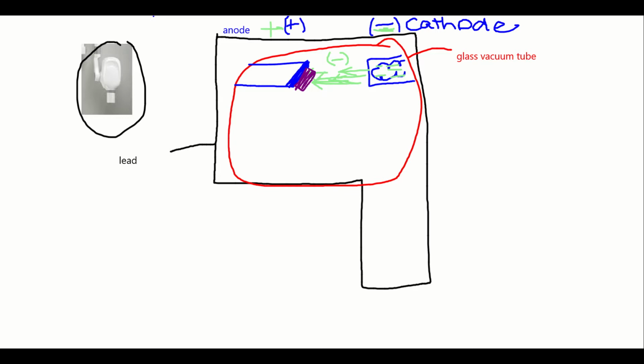You might have heard of a tungsten ring, like wedding rings seem to be popular now, made out of tungsten, and it doesn't change its shape. Anyway, it's a type of metal. So this piece right here is called the tungsten target. Important to remember that for a couple of reasons. So that piece of metal is called the tungsten target.